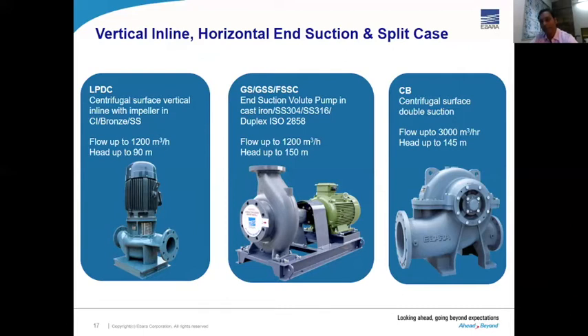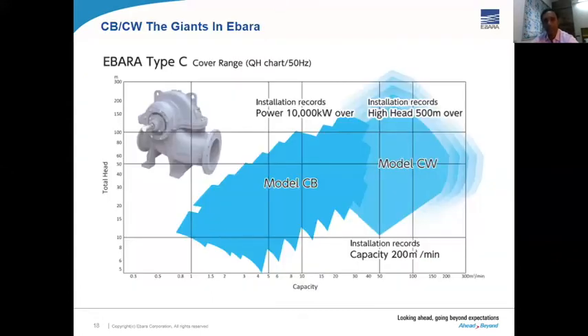In terms of the end suction pumps, the main feature is efficiency; hydraulic efficiency is much higher than most of the competitors, I would say. Then we have the split case pumps, which go up to 3000 cubic meters per hour and have a compact design. Your footprint or pump room size can be reduced because the bearing assembly is compact. We have a short shaft, which is an advantage because the deflection on the shaft also reduces. The large split case pumps, the giant ones, can go up to 200 cubic meters per minute, so we can get into the megawatt range in these pumps.